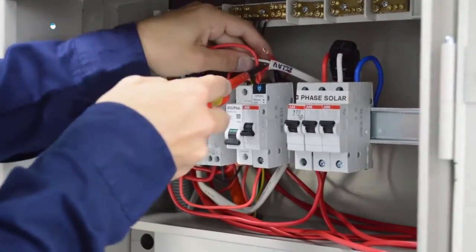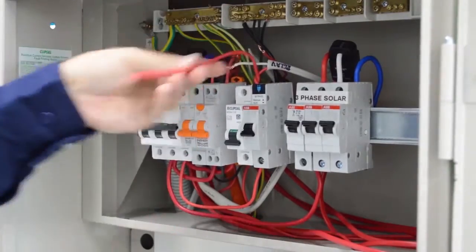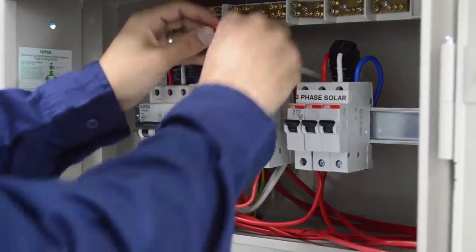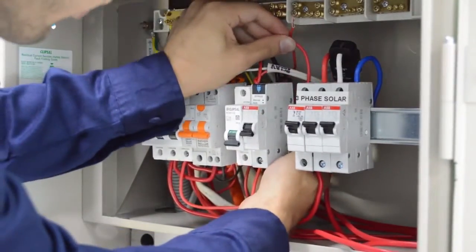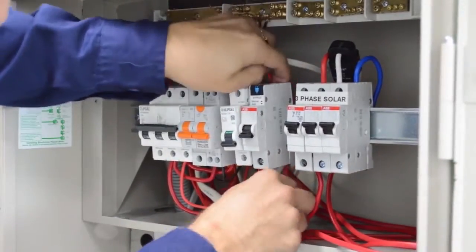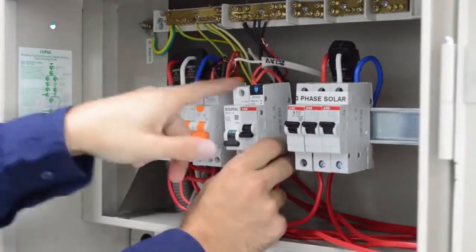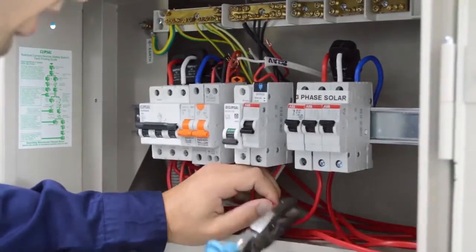One of these, the twin red, will feed the relay line side, and this active we're going to use to feed the line side of the bypass switch. I can't stress enough how important it is to feed the bypass switch from the same load side of the circuit being switched to avoid a dual feed.